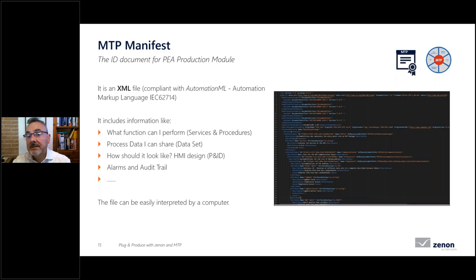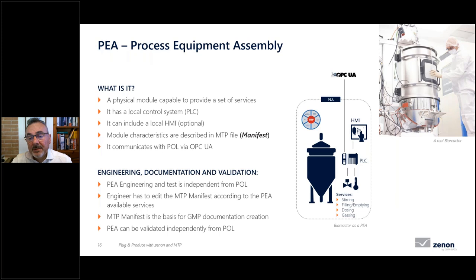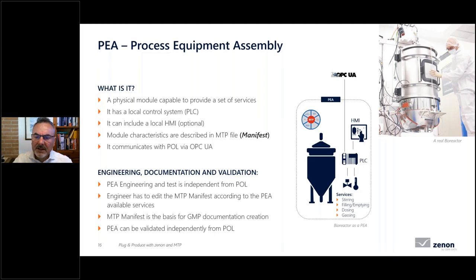The MTP manifest is a computer-readable XML file. The second component is the PEA — a physical mechanical component with local automation such as a PLC, specific services based on its capabilities, a local HMI for local monitoring and control, OPC UA communication with the upper-level system, and the MTP description file.